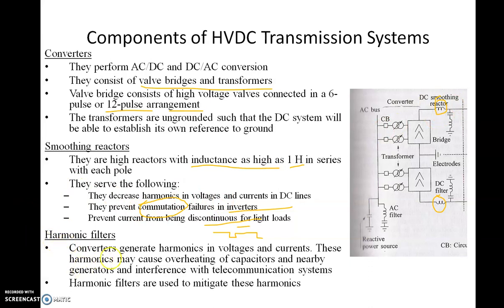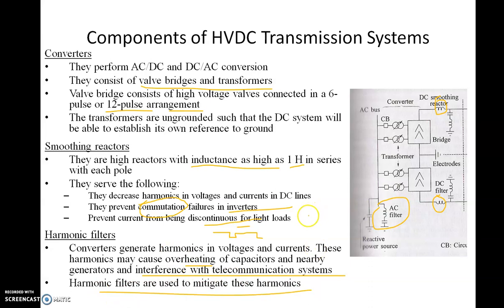Regarding harmonic filters: converters generate harmonics in voltages and currents. We have DC filters and AC filters on both sides. These harmonics cause overheating of capacitors and nearby generators, and interference with telecommunication systems, among other problems. That is why we use harmonic filters to solve this problem.